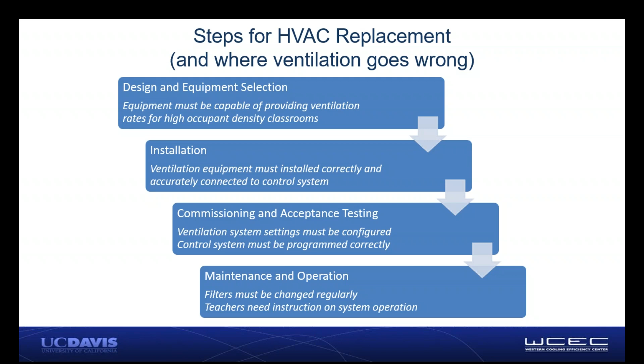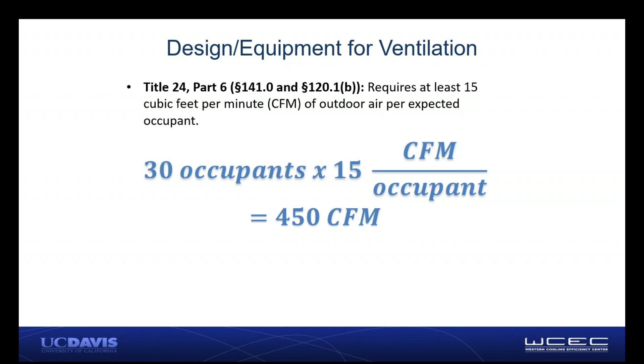So just briefly, what's required in a classroom in California, which, as Renji mentioned, is similar to the ASHRAE requirements. Basically, you need 15 cubic feet per minute of outdoor air per occupant. It can vary quite a bit, but if we just assume for today that a classroom is designed for 30 people, then that is 450 cubic feet per minute, just to give you an idea of the magnitude of how much air you need to move. Next slide.